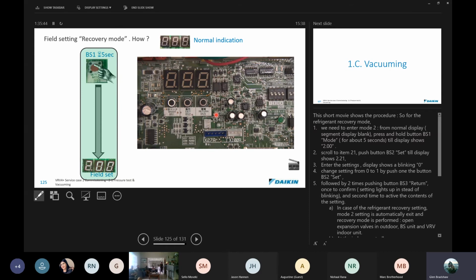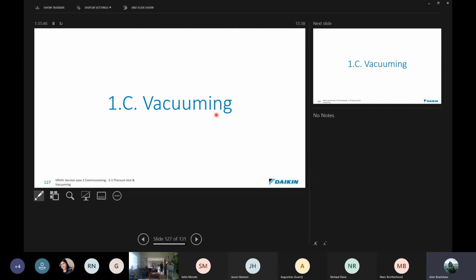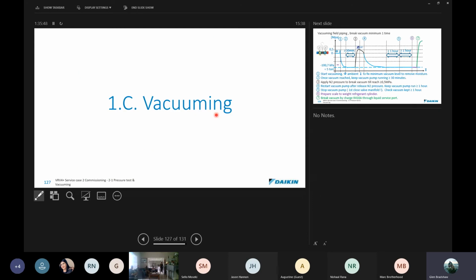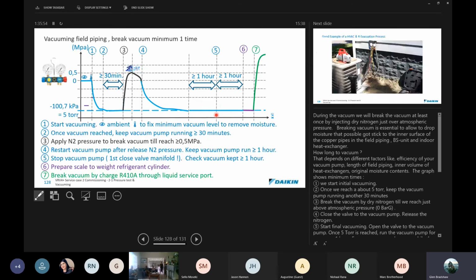All right, so very important to remember those. Okay, vacuuming. Once we've got it into mode 21, and we're going to evacuate the system, you need to remember that starting the vacuum, we need to get down, and we ask for a vacuum of 500 microns.